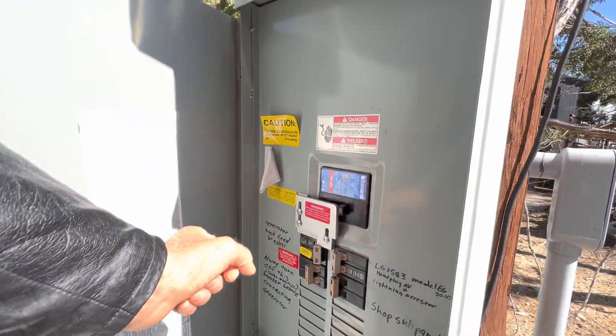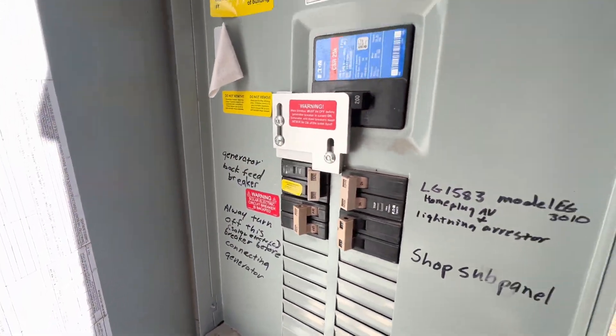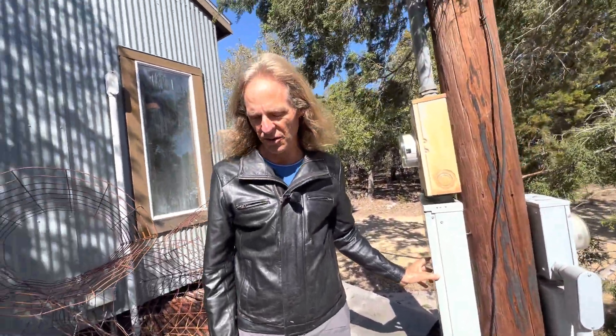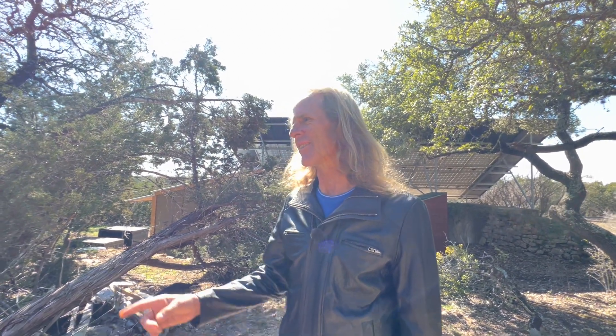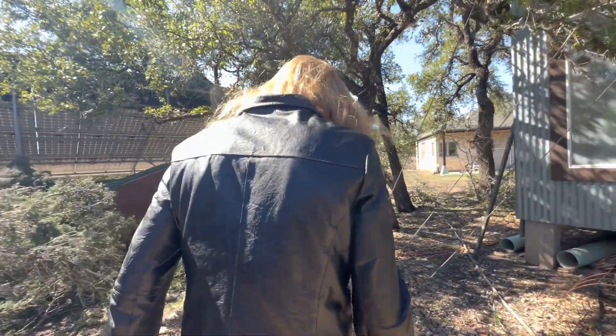With this interlock in place, we also have to turn the solar panel breaker off before we do all that, because you don't want to run solar panels while you're running a generator — when the sun comes out you're going to blow some electricals on your generator. I'm going to do a video on which generator we use and why. Let's go see some of the other layers.